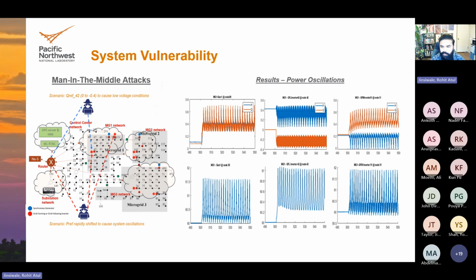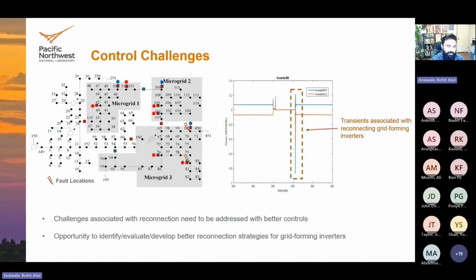Another thing we noticed was particularly associated with inverter reconnection. When grid forming inverters are tripped out of the system and reconnect, the challenge is often that the droop kicks in almost immediately on reconnection and creates huge transients in the power, because you're still synchronizing at that point.